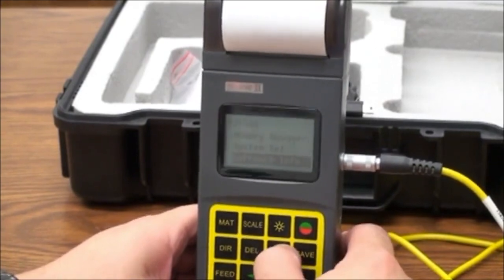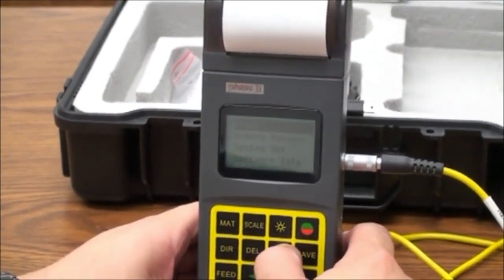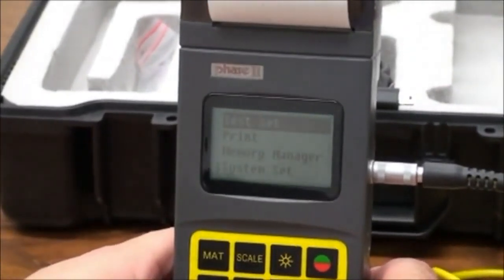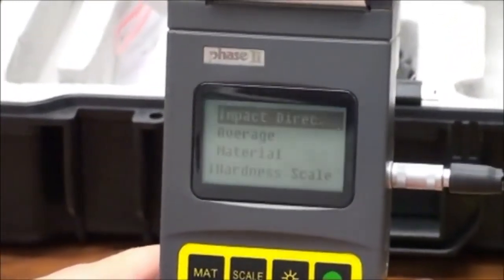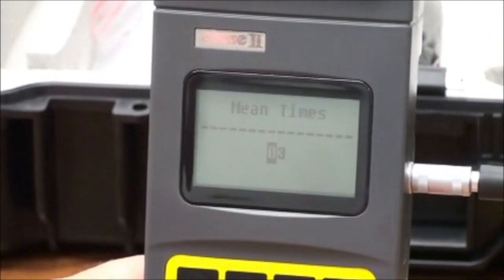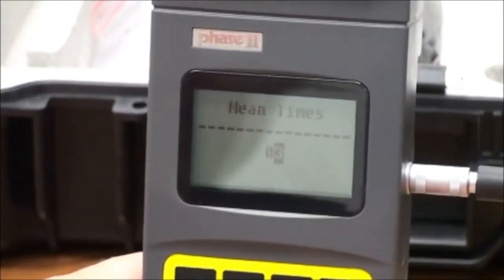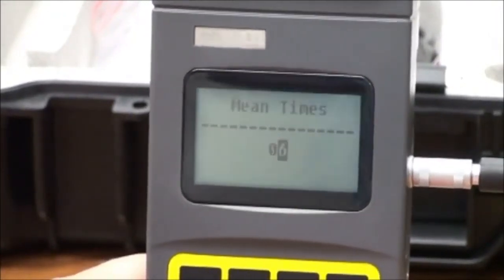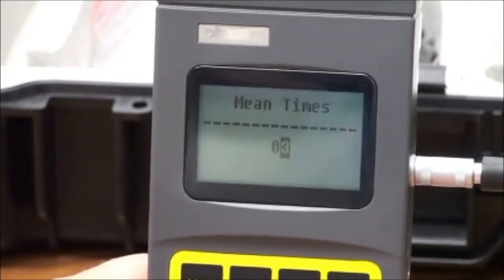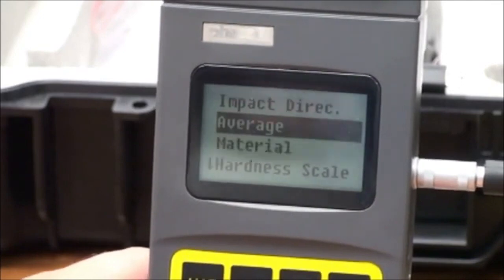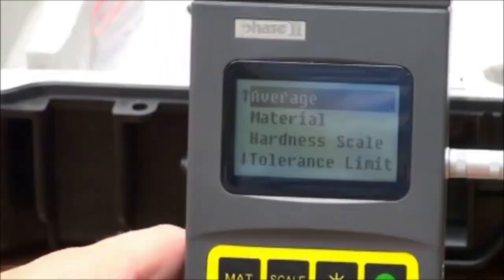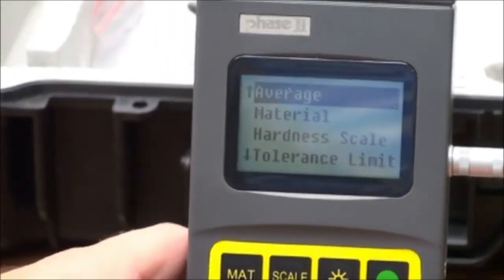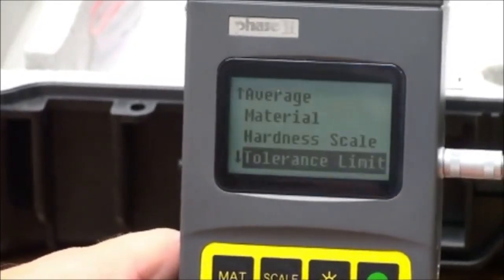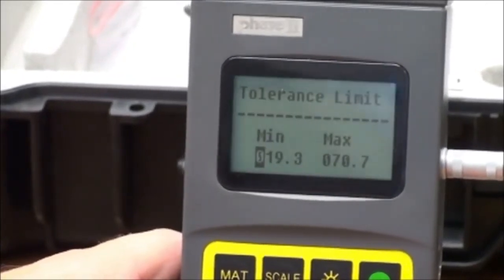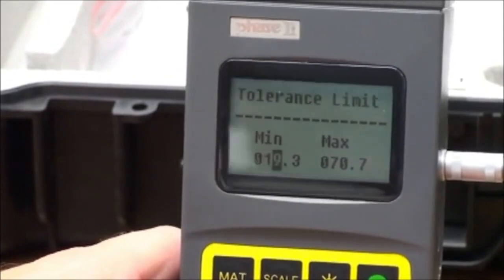Pressing the menu button will give you a choice of modules to enter. Scrolling to test set, we see a new parameter called average. This allows the user to preset how many tests will be taken before the average is displayed. Select your choice with the arrow keys and press Enter to confirm or Escape to cancel. We will also see tolerance. This is used for setting tolerance limitations, allowing you to preset acceptable ranges for a specific job or part.